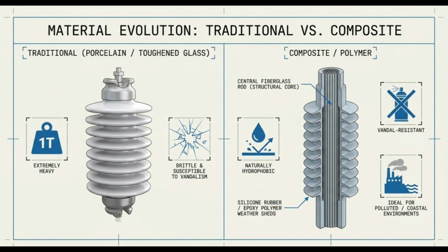First off, they're significantly lighter, which makes them way easier to transport and install. They are also naturally hydrophobic, meaning they literally repel water, which, as you can imagine, is a fantastic trait when you're trying to keep electricity from arcing in a rainstorm. They're highly resistant to vandalism and breakage. But maybe most importantly, they absolutely excel in highly polluted or coastal environments where built-up dirt and corrosive sea salt would normally cause electrical tracking and failure on those older porcelain models.